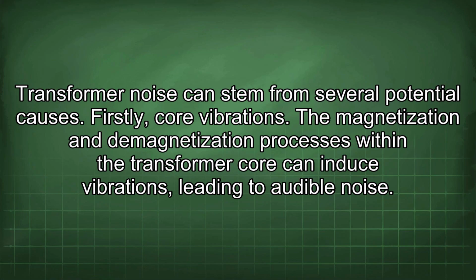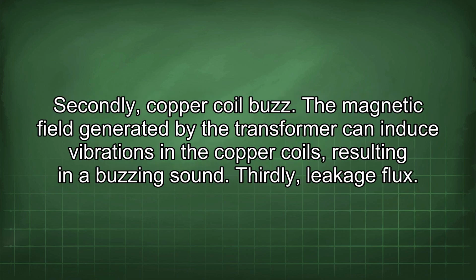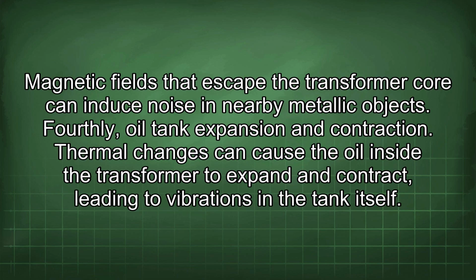Transformer noise can stem from several potential causes. Firstly, core vibrations. The magnetization and demagnetization processes within the transformer core can induce vibrations, leading to audible noise. Secondly, copper coil buzz. The magnetic field generated by the transformer can induce vibrations in the copper coils, resulting in a buzzing sound. Thirdly, leakage flux. Magnetic fields that escape the transformer core can induce noise in nearby metallic objects.